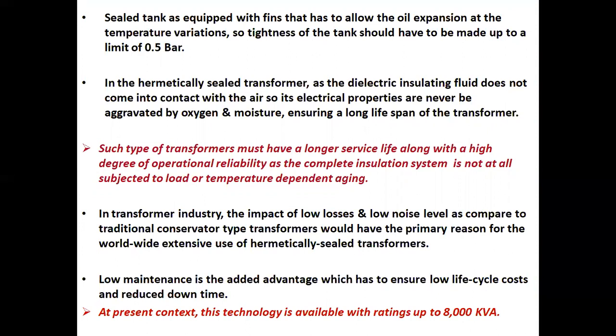The tightness of the tank should be made up to a limit of 0.5 bar. In the hermetically sealed transformer, as the dielectric insulating fluid does not come into contact with the air, its electrical properties are never aggravated by oxygen and moisture, ensuring a long lifespan of the transformer. Such transformers have a longer service life along with a high degree of operational reliability, as the complete insulation system is not at all subjected to load or temperature dependent aging.